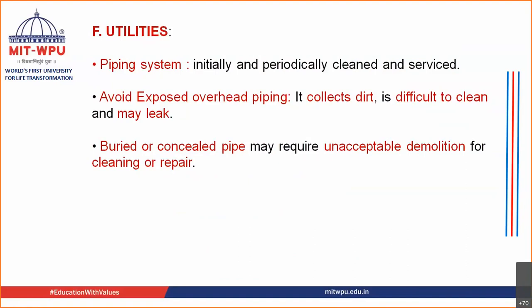Regarding utilities, the piping system must be cleaned initially during installation and periodically thereafter. Overhead piping should be avoided as it collects dirt and is difficult to clean, and may also leak. Concealed or buried piping should also be avoided as demolition is required for cleaning and repair. The piping system should be designed for periodic cleaning and servicing.